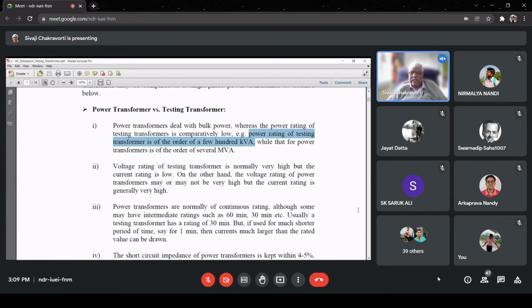Because you don't require a high current for testing insulation. If an insulation draws high current, it is no longer an insulation. So an insulation draws very low current, generally of the order of milliamperes or less. So you don't require more than 1 ampere. Sometimes 500 milliamperes is enough. So it is only of the order of a few 100 kVA. For example, if you come to our high voltage lab, it has a secondary voltage rating of 250 kV, but its current rating is only 0.5 ampere. So its power rating is only 125 kVA.